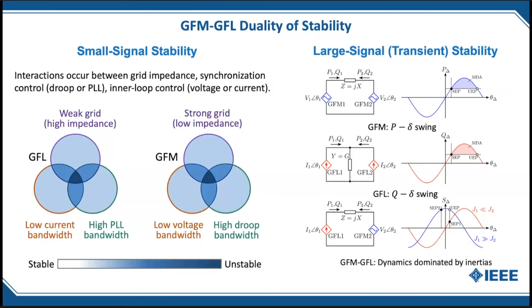That duality carries forward into angle stability. For small-signal effects, it's often said that a grid-following inverter becomes unstable in a weak grid or high-impedance situation — but it's more complicated. It's really about voltage drops across impedances interacting with both the PLL and the current controllers. A combination of poor tuning of the three is most likely to cause instability; in fact, for a weak grid with well-chosen current controllers and PLLs, you can remain stable down to very low values. The dual applies to the grid-forming inverter, which is more likely to be unstable in a strong grid or with a low voltage control bandwidth or high droop bandwidth. This duality carries forward into large-signal transients as well.